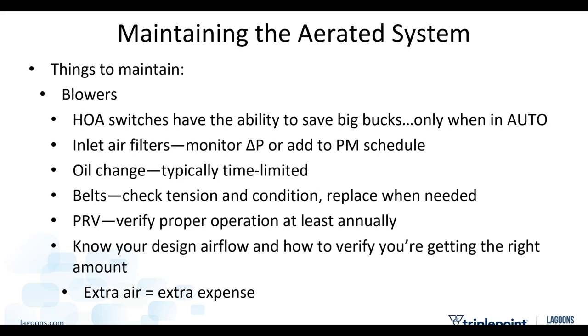Not everyone has the time to do that though. And if you don't have the time to track and trend and keep a clipboard with your delta P measurements on it, please, please, please add it to your PM schedule. Get it on the calendar, do it every month, every quarter, whatever the interval works out to be. But please change those inlet air filters. If they're clogged and dirty, they're robbing your system of efficiency.